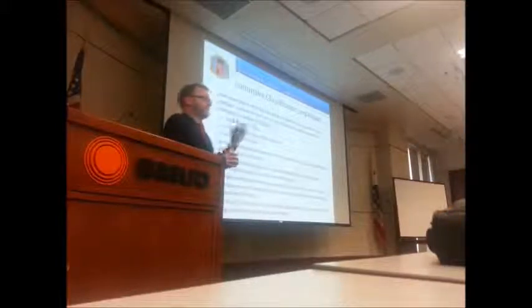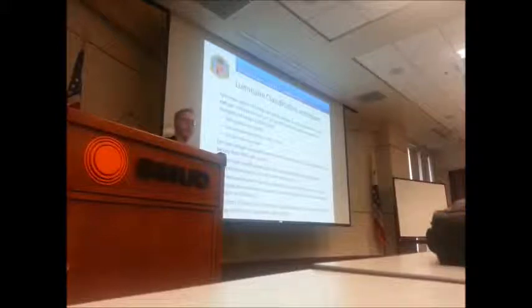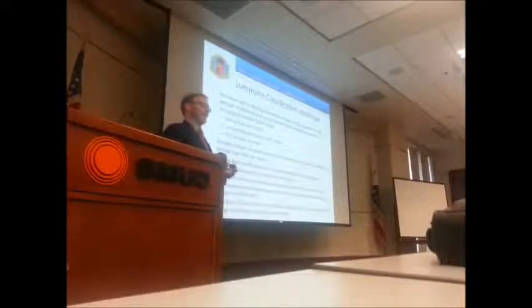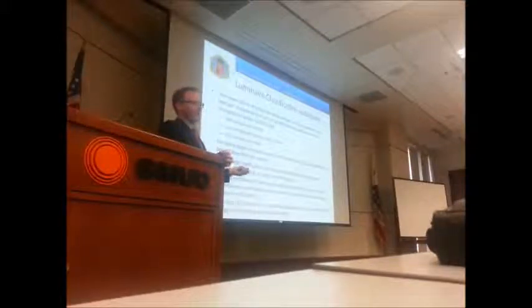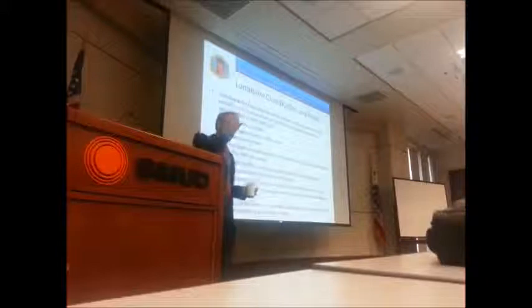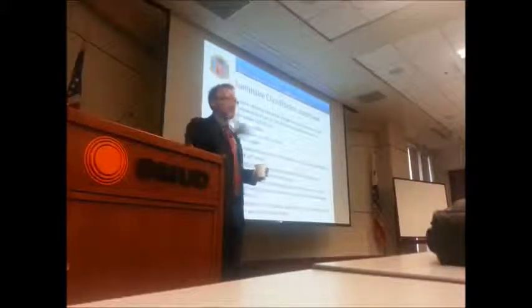But let's say we've got CFLs. You've probably all seen these where the ballast is capable of driving an 18-watt lamp, a 23-watt lamp, a 26-watt lamp, a 32-watt lamp, all from the same multi-watt ballast in the CFL. That's really common. What do we do about that as the people who write code? Do we say, yes, those ballasts are driving 18-watt lamps, but they could drive a 42-watt lamp, so we're going to say you've got a 42-watt luminaire? That wouldn't make you very happy, and it would create a lot of work for building inspectors. They'd have to go around, take the lamps out, and check every ballast for the maximum wattage printed on it.